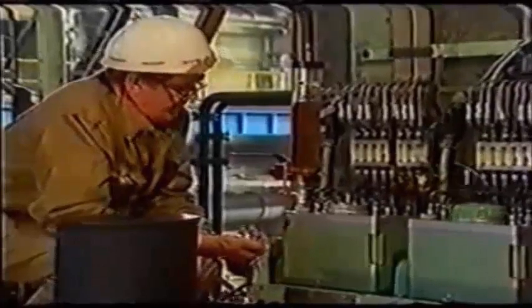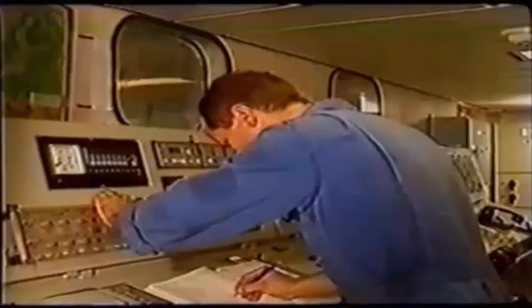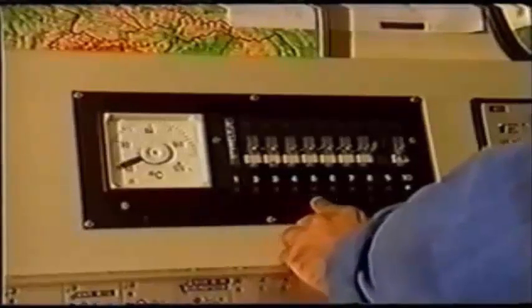The use of heavy fuel oil with high sulfur content is making the job of the cylinder lubricant very difficult. Even high alkalinity oils cannot hope to neutralize all the sulfuric acids which are produced during combustion. The cooling system must be operated so that the cylinder liner temperature is not dropped below the temperature at which the sulfuric acid may condense out on it.